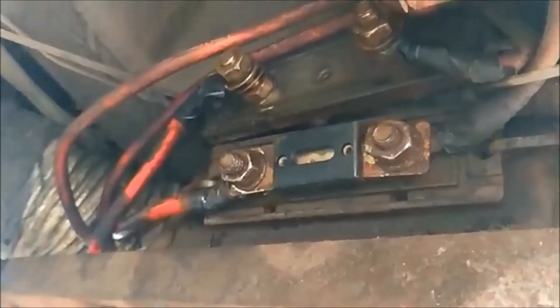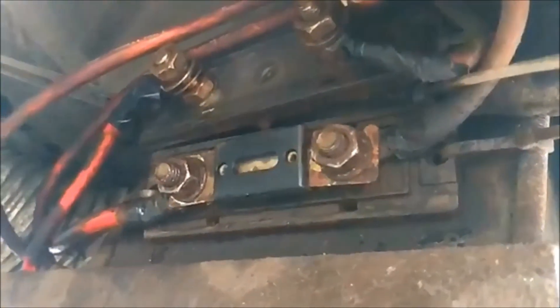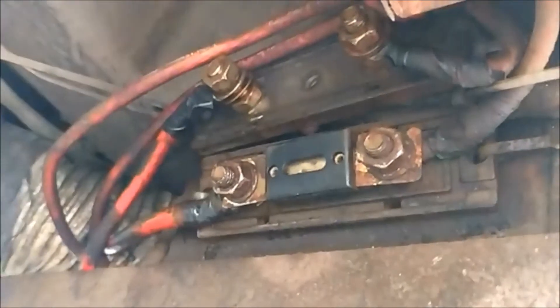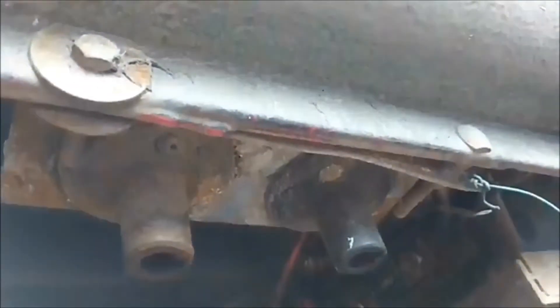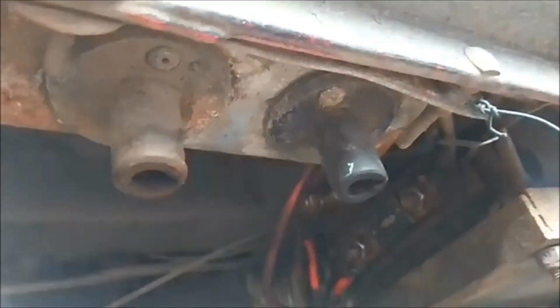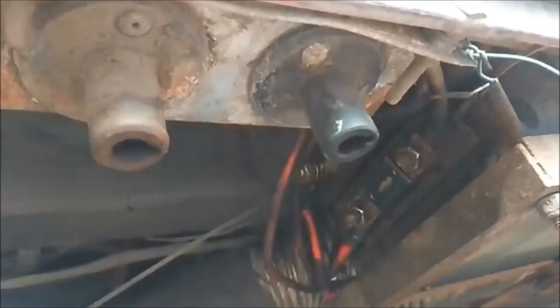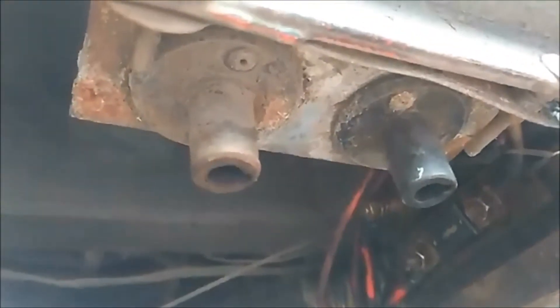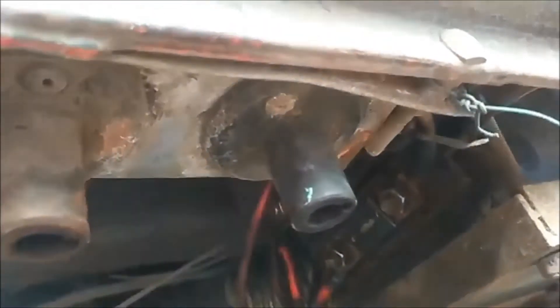Back out in the daytime. As we got the top fuse off, I started on the bottom and there was an awful noise of plastic — I guess I'm going to have to be careful with that one. I need to get that one off to isolate these two switches and see what's been going on. I mounted them that way thinking water would not get up into them, but I think it's got over the top and come down from above, and got into them from the back — because we have all this green crud.